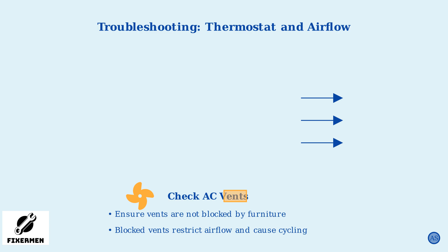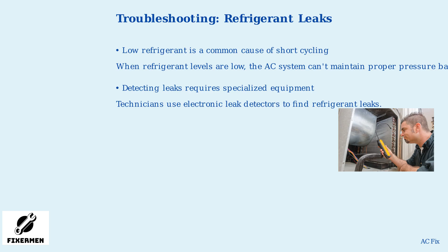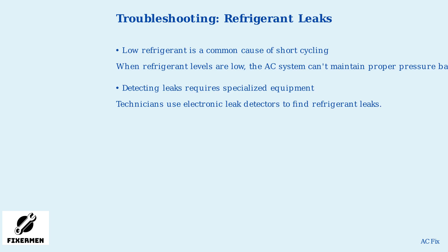Low refrigerant levels are a common cause of short cycling in air conditioning systems. When refrigerant is low, the system cannot maintain proper pressure balance, causing the compressor to cycle on and off frequently. Unfortunately, detecting refrigerant leaks requires specialized equipment like electronic leak detectors. These tools can pinpoint even small leaks that might not be visible.